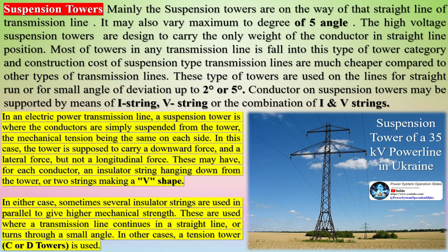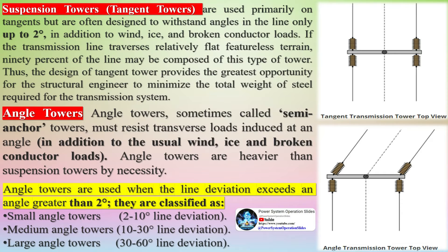Suspension towers are mainly positioned along the straight line of a transmission line, and may vary up to a maximum of 5 degrees of angle. High-voltage suspension towers are designed to carry only the weight of the conductor in straight-line position. Most towers in any transmission line fall into this category, and their construction cost is much cheaper compared to other types.